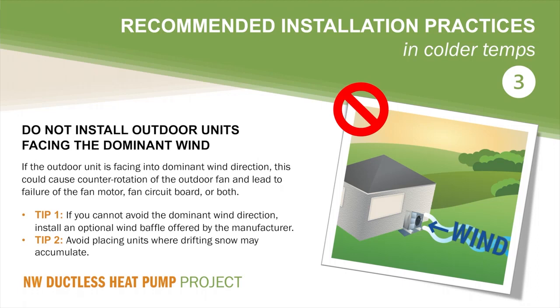There are 2 tips we can offer. Number 1, if an alternate installation location cannot be found, use an optional wind baffle offered by the manufacturer. Number 2, be mindful of drifting snow in addition to wind, and consider combining several of the other outdoor unit installation techniques we will describe in a few moments. The end goal with this practice and several others is to choose the outdoor installation location wisely. We need to make sure that the heat pumps we install operate reliably for years, because a system that is finicky and prone to service issues is certain to disappoint the customer.